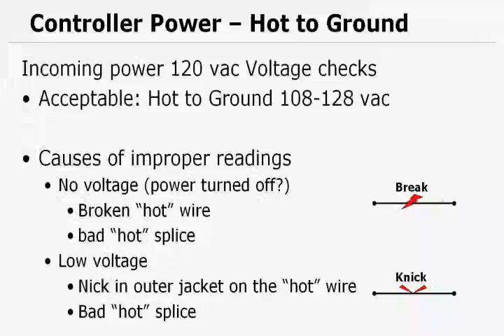So looking at that a little bit more, that 120 volt reading that we had, again, acceptable as 108 to 128, perfectly good reading at 120 volts. If we don't have that reading, some of the causes of an improper reading: if we get no voltage, let's go look and see if the power is turned off, or it could be that we have a broken hot wire, or we have a bad hot wire splice. If we have a low voltage reading, something below 108 volts, it may be that the hot wire has a nick in the outer jacket, or we have a bad hot splice somewhere in the power wire.